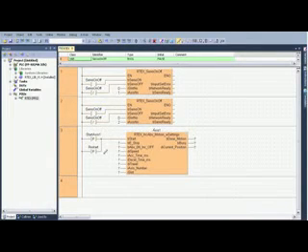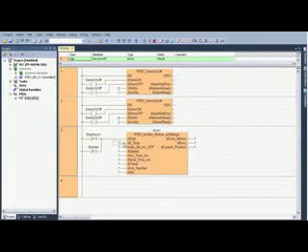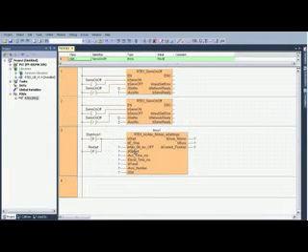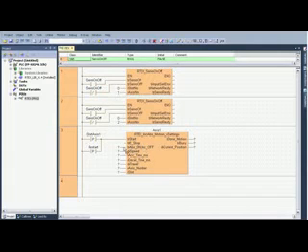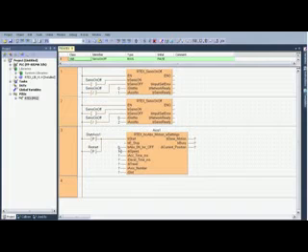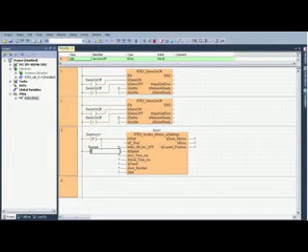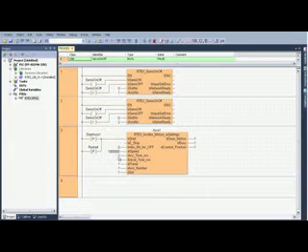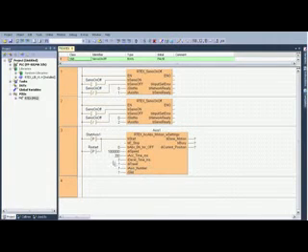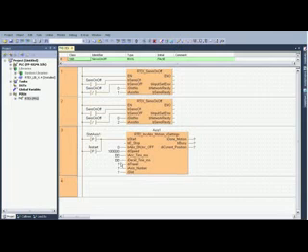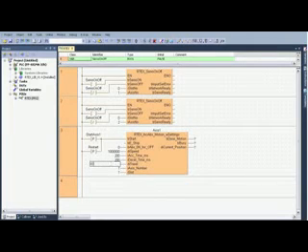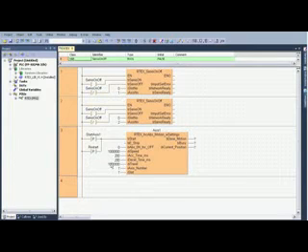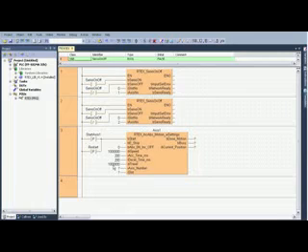Okay so now everything else is in my parameters. I'm going to delete stop, I don't need that. The first parameter here is whether we're selecting this function block as absolute motion or incremental motion. I want this to be incremental, so the parameter for that is zero. If it were absolute it would be one. Now the speed is in pulses per second. I'm going to set this at one million. So it's going to be about one revolution per second. Acceleration time I'm going to do 200 milliseconds. Deceleration time also 200 milliseconds. My travel I'm going to do one million pulses. That's going to give me right about one revolution. It's a little less than one revolution but we're going to round off for simplicity's sake.